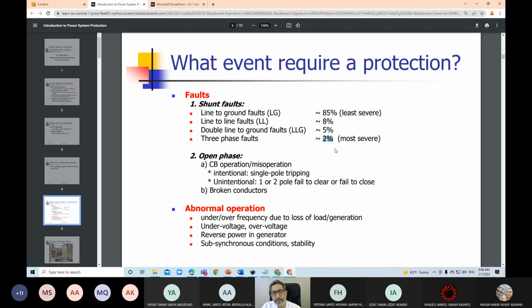These are shunt faults. We also have open phase faults, like when you give a command to a circuit breaker to open it, but two phases open and one stays, or you try to close a breaker, two phases close and one stays open. So you will have a system that is operating on two phases. We call this an open phase condition. Okay. So that's an imbalance situation. It's not a shunt fault, it's an open phase fault. And that's also something you want to detect and disconnect the system.